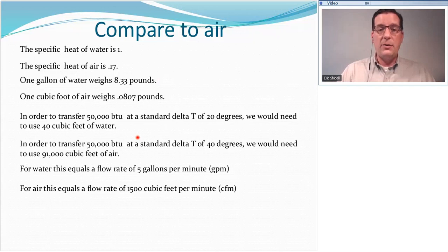If we're going to transfer 50,000 BTU in a delta T of 40 degrees for air, we would need 91,000 cubic feet of air. The delta T was only 20 when it comes to air. We're probably talking closer to 180 or 200,000 cubic feet of air. Now for water, this means we're going to have a flow rate of 5 gallons per minute. We need to move 5 GPM to do that work. To do that same amount of work using air, we're going to be looking at a flow rate of about 1,500 cubic feet per minute.